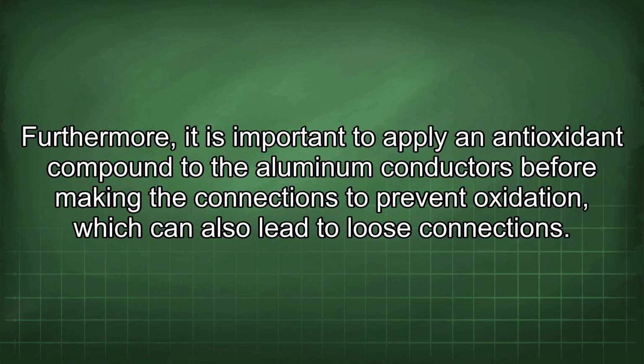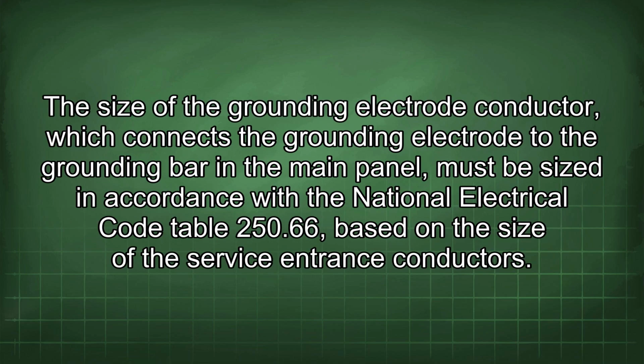Furthermore, it is important to apply an antioxidant compound to the aluminum conductors before making the connections to prevent oxidation, which can also lead to loose connections. The size of the grounding electrode conductor, which connects the grounding electrode to the grounding bar in the main panel, must be sized in accordance with the National Electrical Code Table 250.66, based on the size of the service entrance conductors.